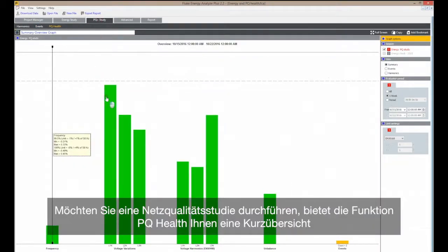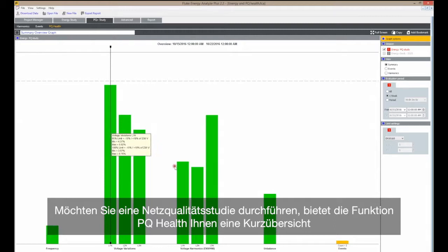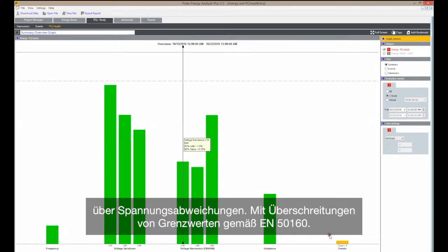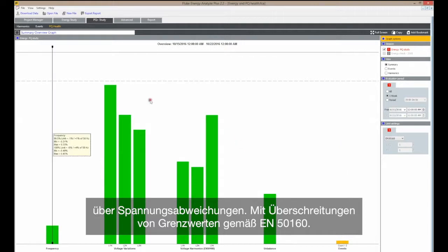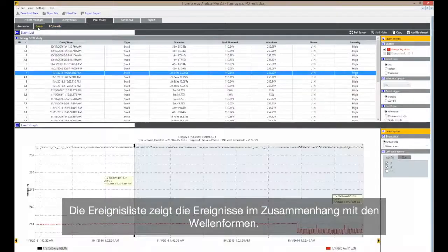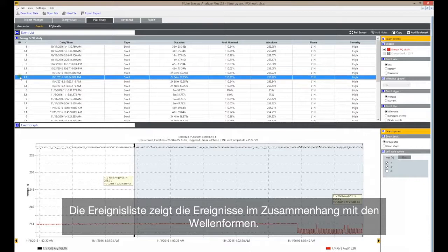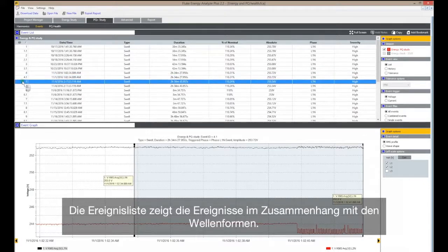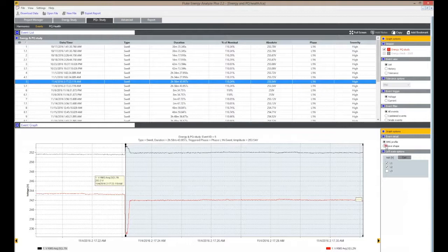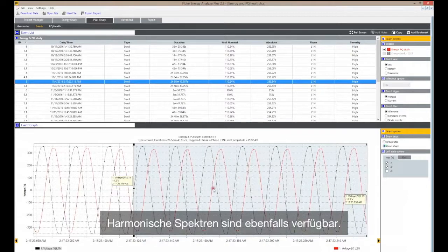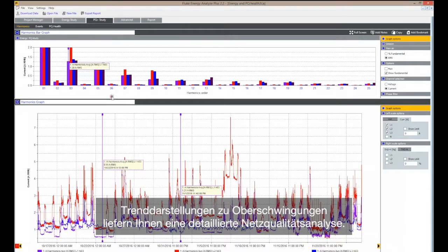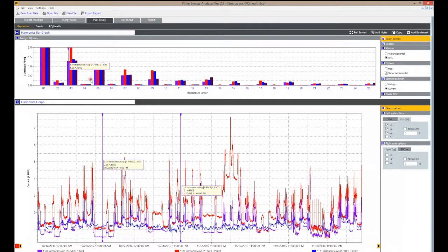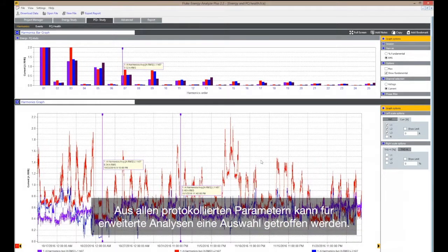If you want to perform a power quality study, PQ Health gives a quick overview about voltage variations with exceedances of limits according to EN 50160. The events list shows the events that took place along with wave shape details. In addition, harmonic spectra are available, and trend plots on harmonics give you a detailed power quality analysis from all the parameters that were logged.